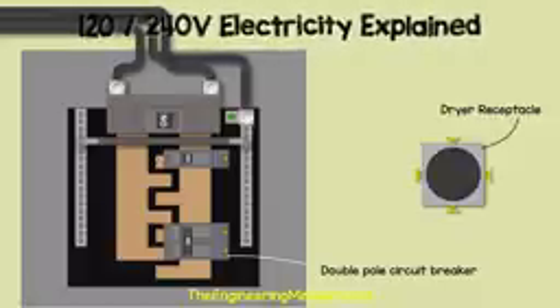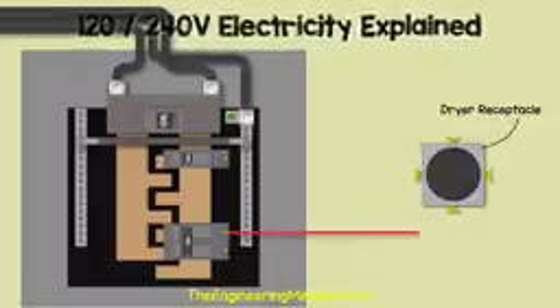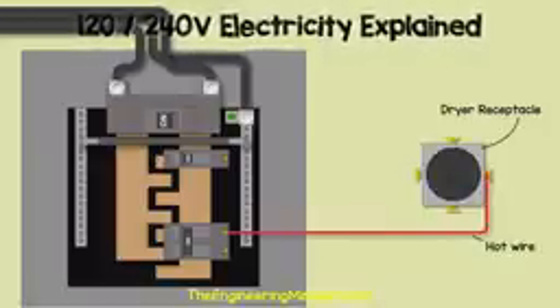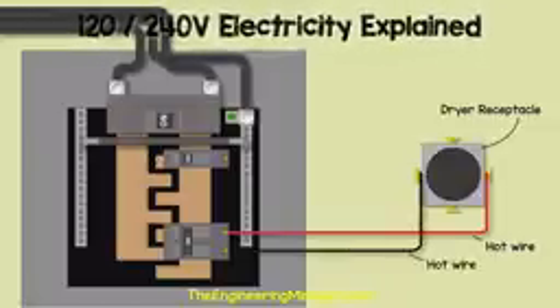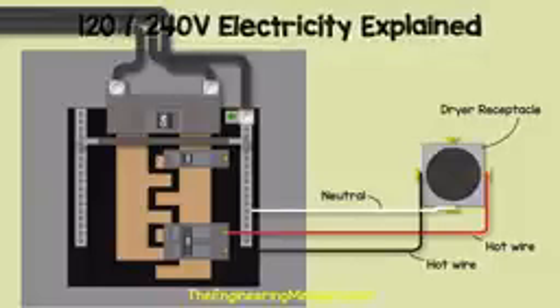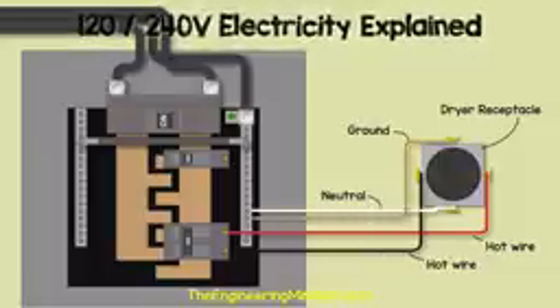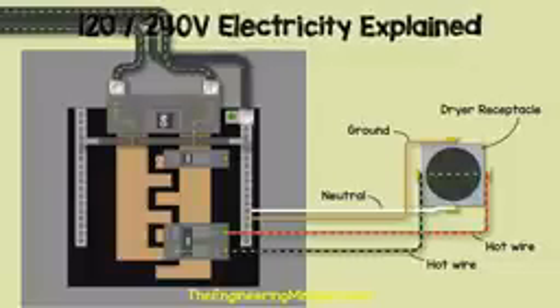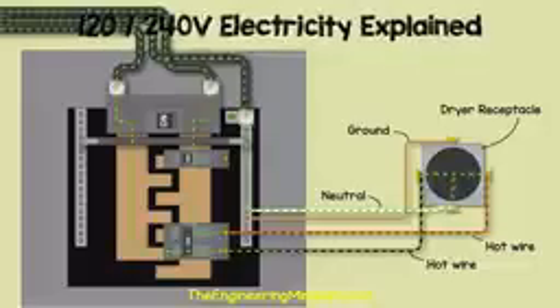If we look at the dryer circuit example, we run the red hot wire from the circuit breaker, which is connected to the main bus bar number 2, and we run this to the receptacle. Then we run our black hot wire from the other terminal of the circuit breaker, which is connected to bus bar 1, and we connect that to the receptacle also. In this case, we have the neutral wire connected between the neutral bus bar and the receptacle, which will allow us to get either 120 or 240 volts from the outlet. Then we have a ground wire to provide a safe route for any fault current. Now we can either connect across the two hot wires for our 240 volt connection, or between the hot wire and the neutral wire to get 120 volt connection.